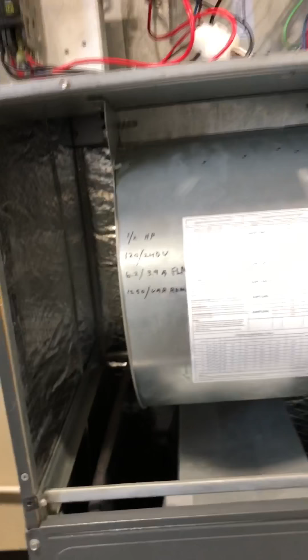The sequencer will bring those heating elements on in a sequence, meaning they don't come on at the same time. If everything works right, the blower motor and the first element will come on together, and then the second element, third element, fourth element, however many elements you have in the system, will come on in a sequence. And they'll also turn off in a sequence. The sequencer does that. It's a control. It does high voltage; we have high voltage wires right here, these red and black wires, to control the strips.